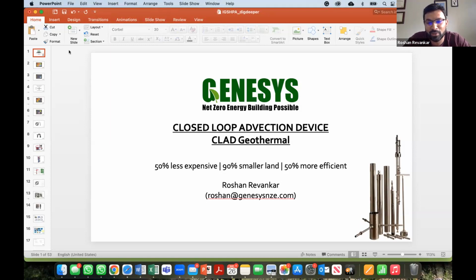And the second question, in terms of maintenance, it's kind of neat. Again, reiterating the fact that the entire system can be lifted up. If there is any scaling on the housing or casing, the way this would be done is you pick it up just like a water well pump, pressure wash it, and put it back into the existing well. The bottom of the CLAD unit would not sit at the bottom of the well. It would be about 5 feet from the bottom of the well, just to protect the bottom of it and make sure the pump has enough flow around it to push the water through the CLAD unit.